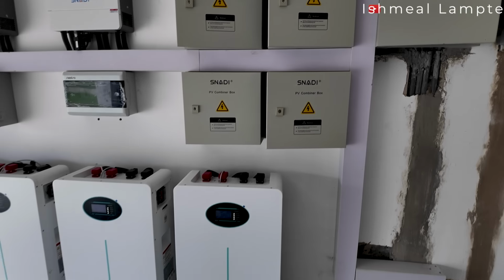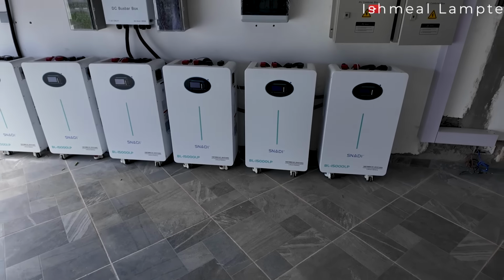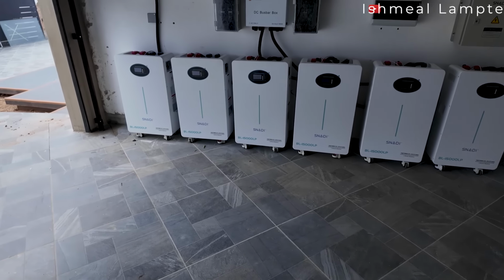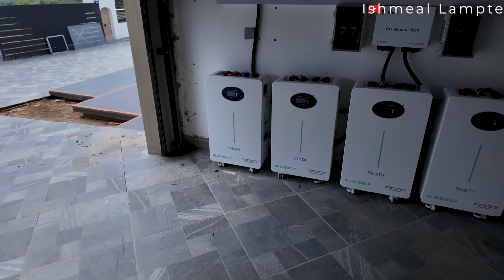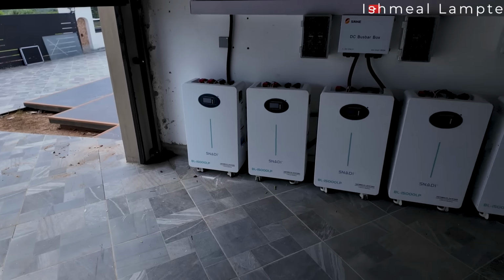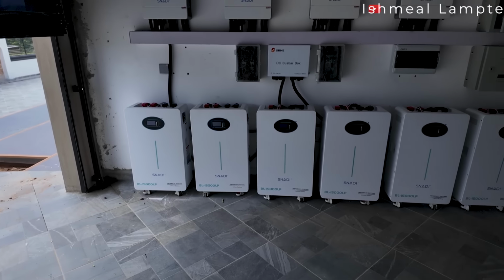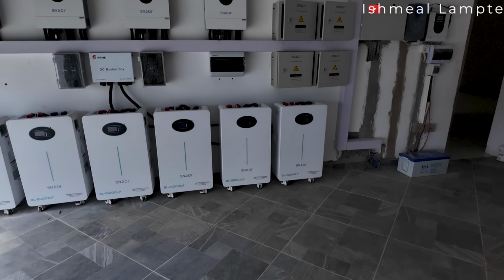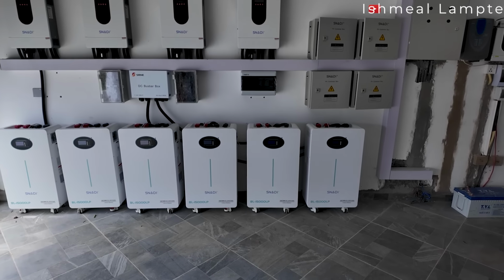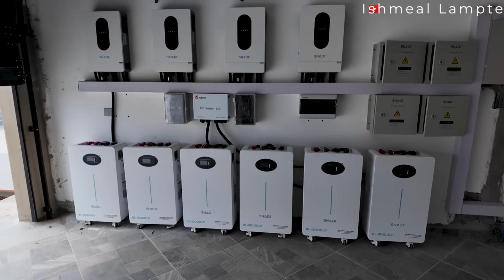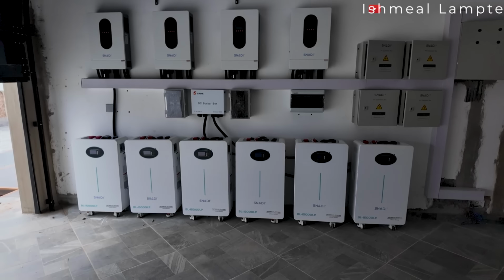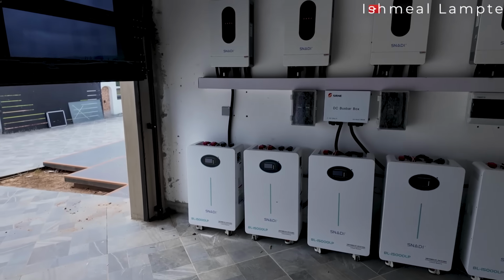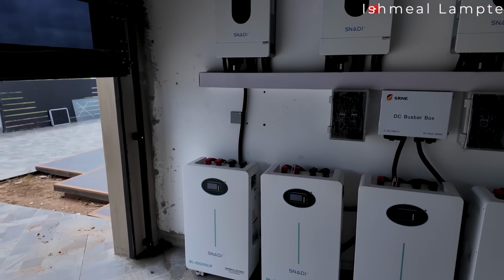So this is the ATS that we have here. Now let's look at a battery. These are 16 kilowatt hour each, lithium iron phosphate batteries, giving us a total capacity of 96 kilowatt hours, close to 100 kilowatt hours. This can do a lot. Looking at the load for the house, it's able to handle all those loads, so this is a good capacity for the system, which is working very well.